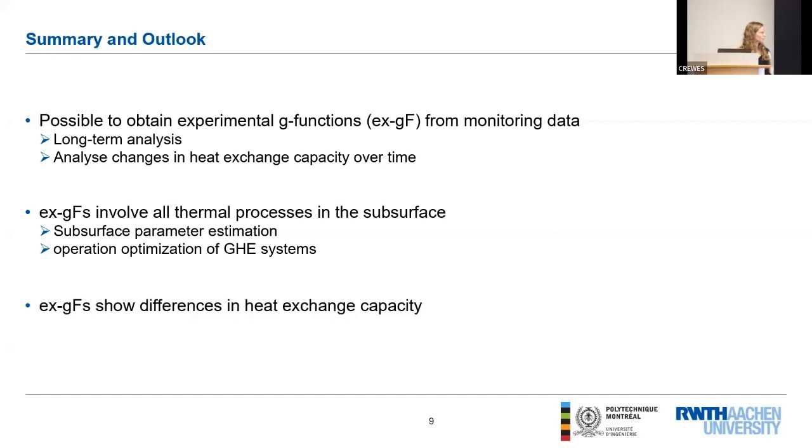And last but not least, we have seen that there are some differences in the heat exchange capacity of the boreholes. And this is due to many different reasons. For example, the number of neighboring boreholes or the current temperature of the borehole. And analyzing this in more depth is one of my next steps.